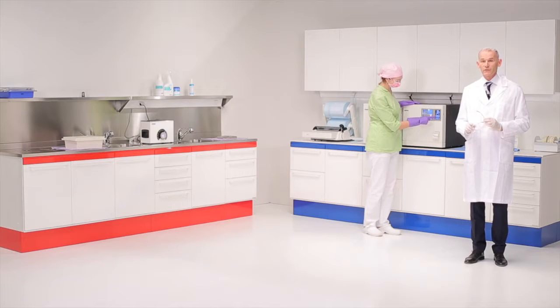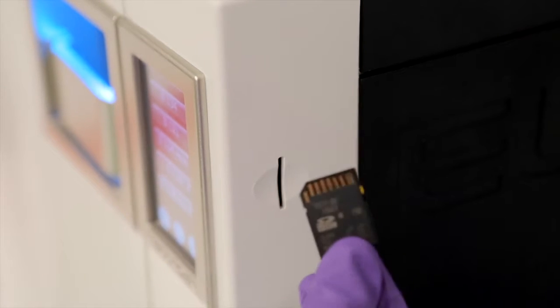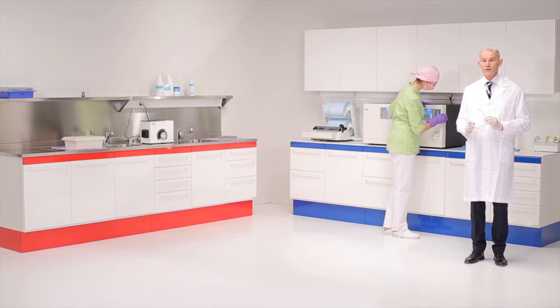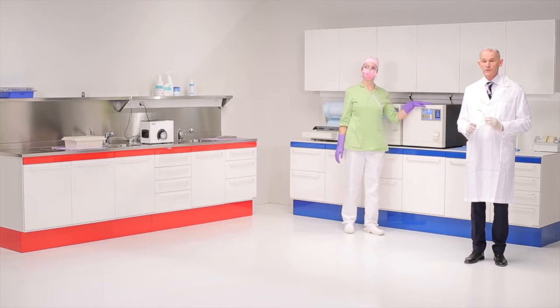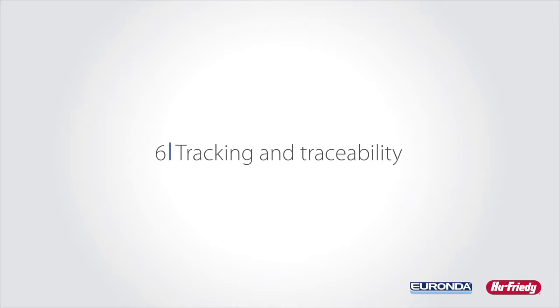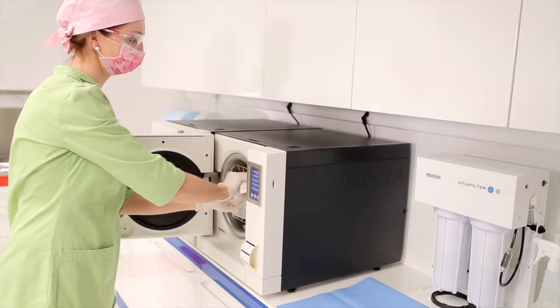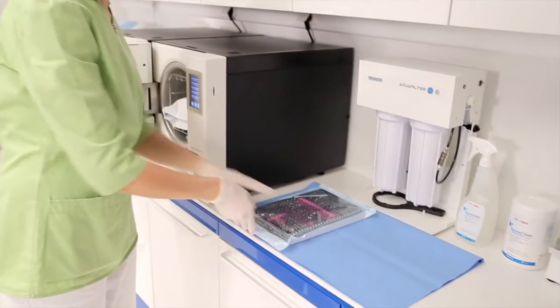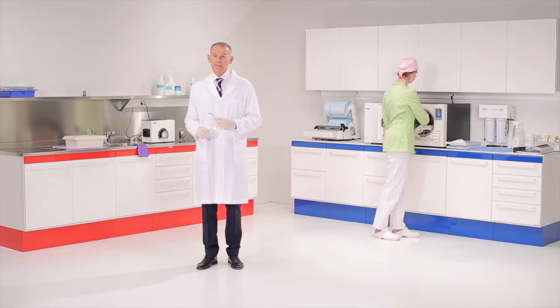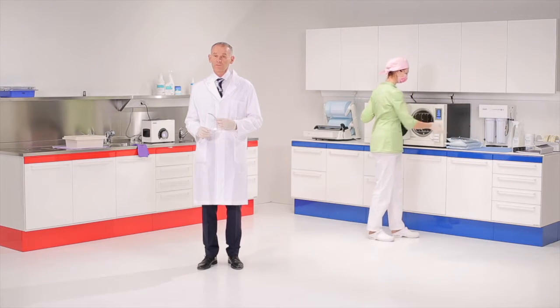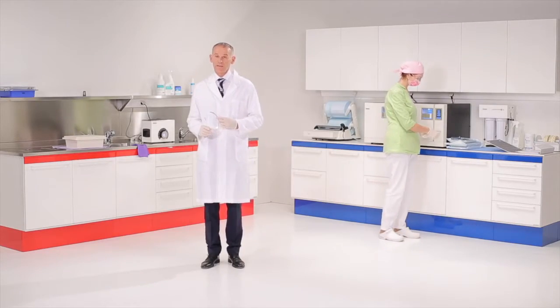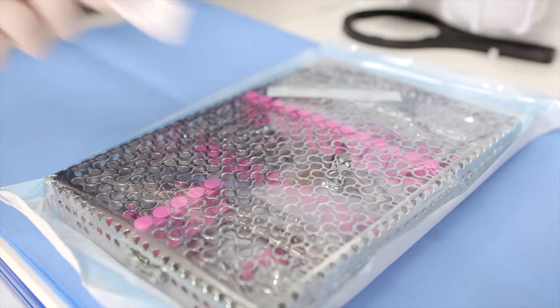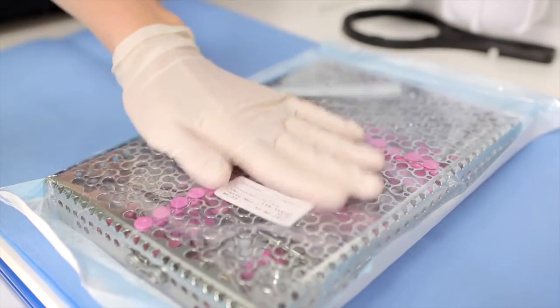The adhesive label printer enables labels with barcodes and simple labels with expiry dates to be printed. The data concerning the sterilization cycles are stored on an SD card to enable traceability, while the optional e-Wi-Fi connectivity system enables the remote transfer of stored data. The saving of the data and therefore their traceability enables all the stages of the sterilization cycles to be monitored and the following information to be stored: autoclave serial number, number of cycles, type of cycle carried out, date of sterilization, date of expiry for that cycle depending on the storage, code and name of operator. These data are stored on the SD card and printed on labels that will be affixed to the sterilized bags and in the sterilization register.